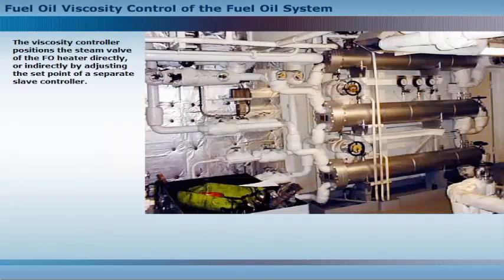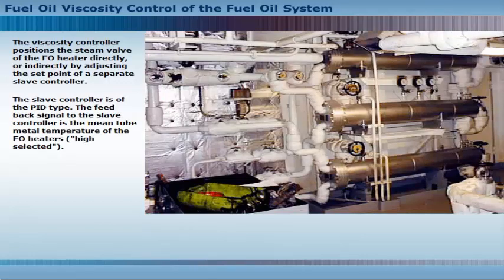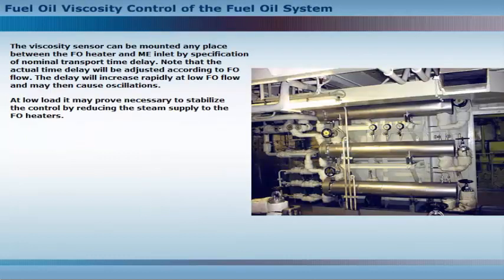The viscosity controller positions the steam valve of the fuel oil heater directly or indirectly by adjusting the set point of a separate slave controller. The slave controller is of the PID type. The feedback signal to the slave controller is the mean tube metal temperature of the fuel oil heaters. The viscosity sensor can be mounted any place between the fuel oil heater and ME inlet by specification of nominal transport time delay.